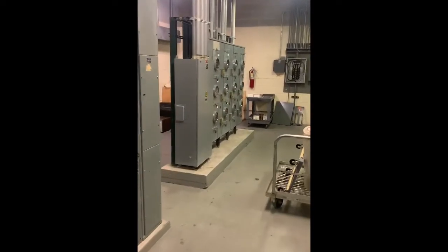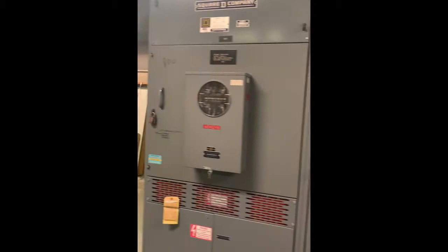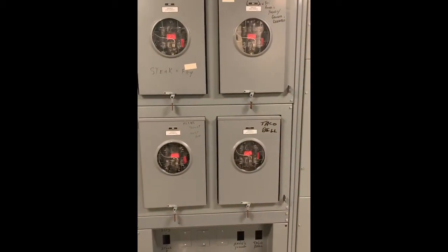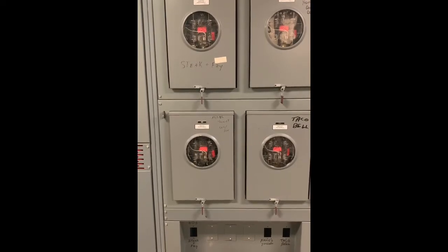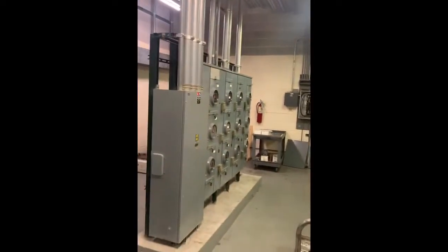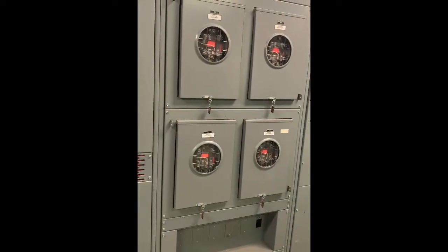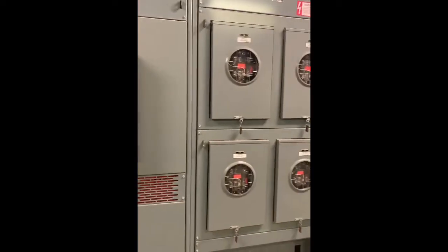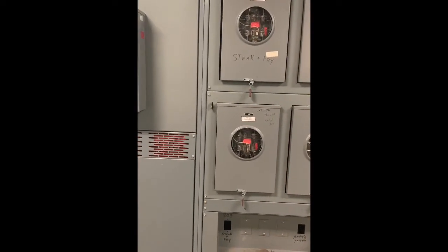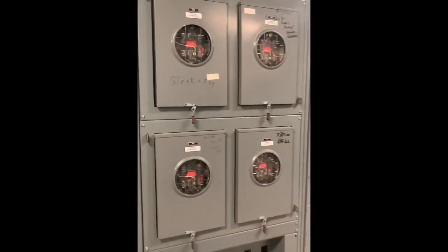Well, this is just one floor, okay? And although there was quite a bit of tenants that were being supplied from this one floor, it is kind of typical of what we would find on a lot of the other floors. So when this building was built back in the 80s, we got a huge discount from ComEd if we did all electric heat. And when they were designing and laying this building out, there would be multiple meters for each tenant, whereas that really doesn't make sense nowadays. Nowadays, people would probably tend to minimize and go with the least amount of meters as possible.